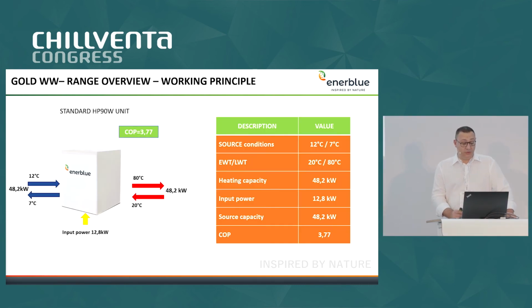As a working principle, we saw before, we have a water-to-water unit, so the input power is more or less 13 kilowatt. On the source side, we are working with 20 inlet water temperature and 80 leaving water temperature, with a heating capacity of more or less 50 kilowatt, while on the source side we are working with 12/7, so standard working temperature, with a little bit lower source capacity. In this case, the COP is 3.77, so it's a very, very good efficiency, and we can use this unit for replacement of gas boiler and so on.